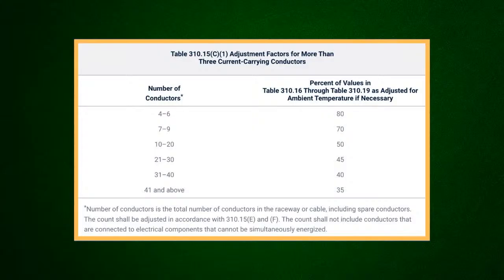I want to point out one other thing. Here is the table, and I don't care about the percentages and all that. I just want to look at the bottom for number of conductors. It says number of conductors is the total number of conductors in the raceway or cable. It's not saying cables all together. It's saying it's in the raceway or the cable, including spare conductors. This count shall be adjusted in accordance with 310.15 E and F. That's where you got your neutral and equipment grounds. And it basically says the count shall not include conductors that are connected to electrical components that cannot simultaneously energize. Yeah, there's your diversity right there. I don't know how much more clear this can be.